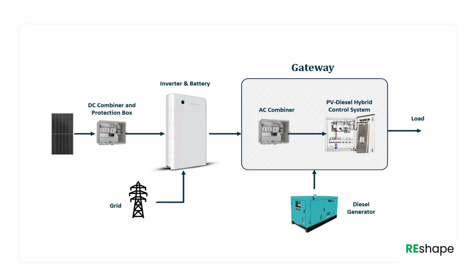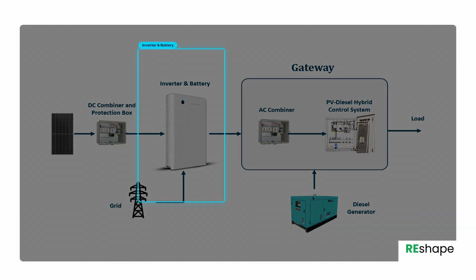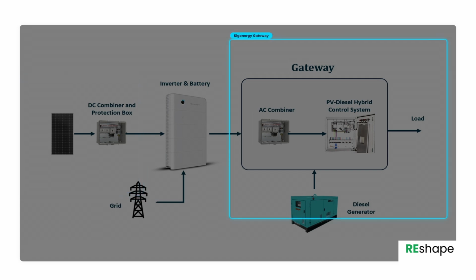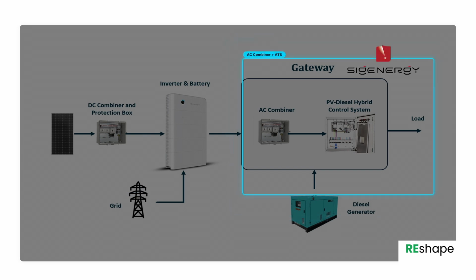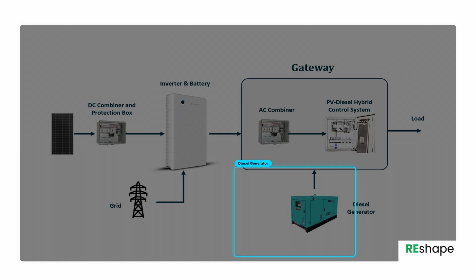Solution 2 uses one 30 kW 3-phase inverter capable of supplying 100% unbalanced load. In other words, it can behave as 3 independent single-phase outputs while being one device. It reduces cabling and wiring labor and simplifies system integration, especially when you use a SigenErgy system with a dedicated gateway that combines AC combiner, PV diesel hybrid controller, including ATS.